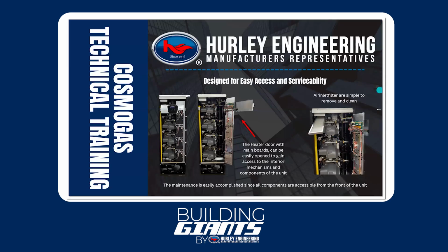So Daryl, is that a cleanable filter? It is a cleanable filter. So it's a directional filter, right? And there's a picture here in a second, but you can actually spin that filter 180 degrees and use both sides of it, but you can't flip it. If you flip it, then the direction will be wrong. But in the meantime, you can clean it too. There are provisions in the manual that comes with it that this filter is cleanable. Thanks.